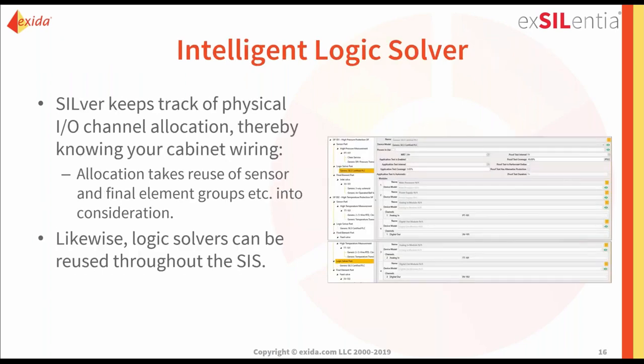The intelligent logic solver feature tracks physical IO channel allocation, so the tool essentially knows what your cabinet wiring should look like. For example, if you have redundant transmitters, you may decide each input goes to a separate input module — if you specify that, the tool takes it into consideration. Logic solvers can be reused throughout the various safety instrumented functions or the entire safety instrumented system.